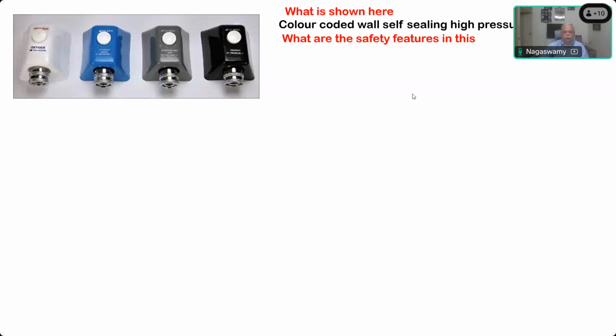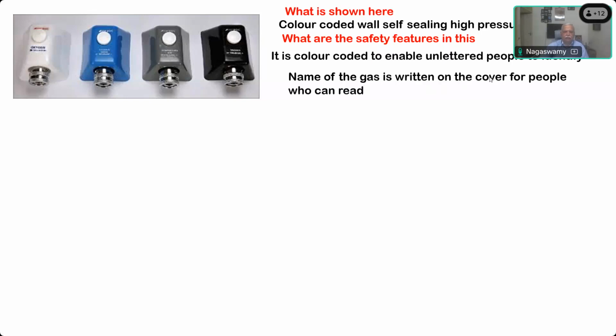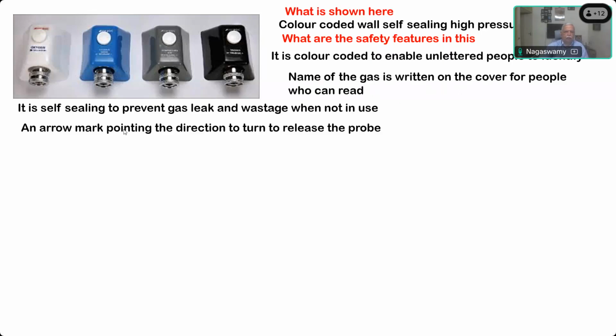Okay, what are the safety features in this? Somebody said diameter index safety system. They are color coded and they have diameter index safety systems. And also, the point I told you, the name of the gas is also written here. So it is color coded to enable unlettered people to identify that. The name of the gas is written on the cover for those who can read. It is self-sealing to prevent gas leak and wastage when not in use. An arrow pointing the direction to turn to release the probe is also given here.